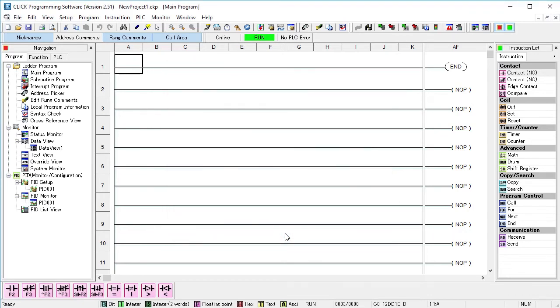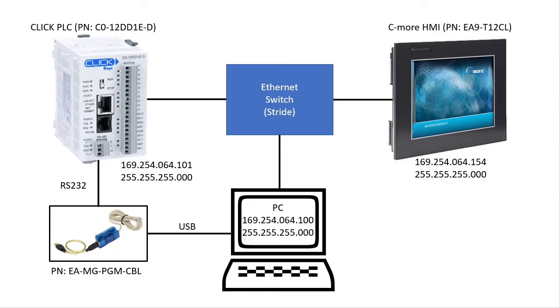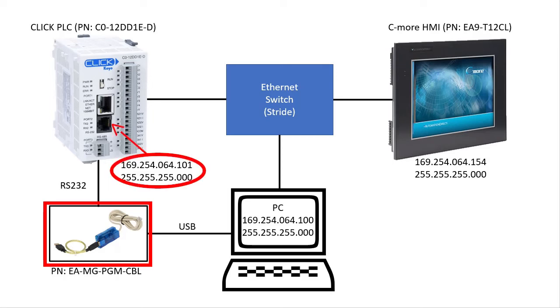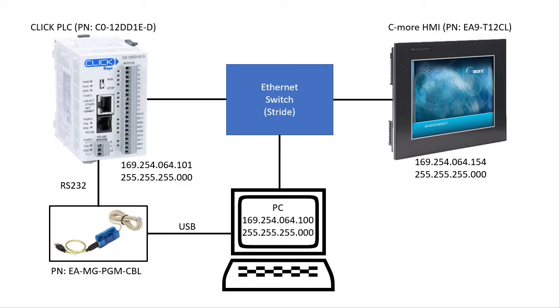This is important. The IP address isn't in the Click PLC until you transfer the project to the PLC. So don't forget that step. Which explains why we are using this USB to RS232 converter to get the IP address set up. We can't talk to the PLC over Ethernet until it has a compatible address.